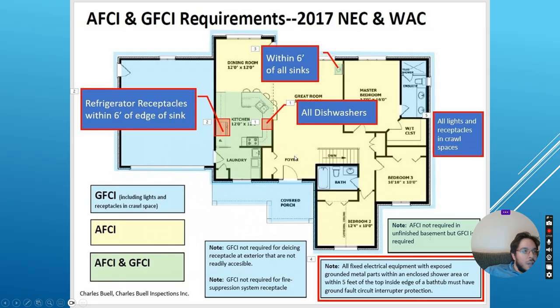Now the other rule is you can't use an AFCI receptacle. It has to be an AFCI breaker that protects the whole circuit, because the receptacle only protects us at the first receptacle and then further down. It doesn't protect us between the panel and the first receptacle. So in Canada you're allowed to put an AFCI receptacle on the first receptacle if the wiring between the panel and the first receptacle is metal. So it can be either armored cable or TECK cable or an EMT conduit, because then there's no arc flash risk there.